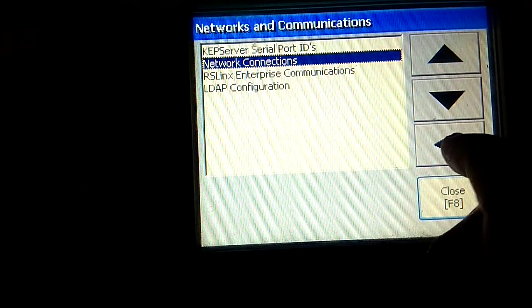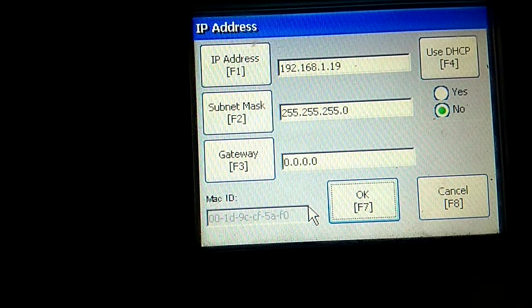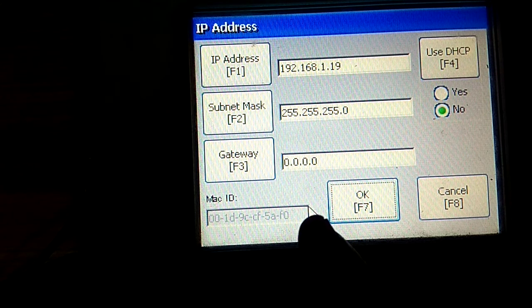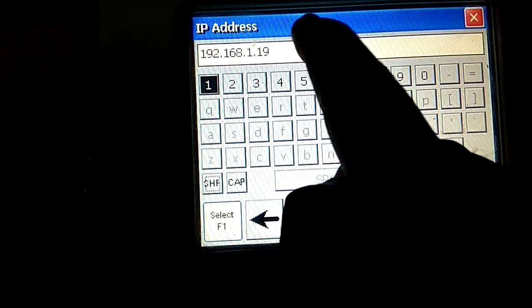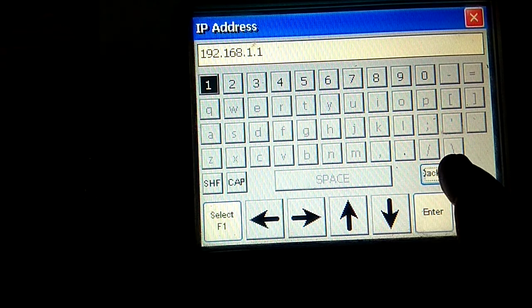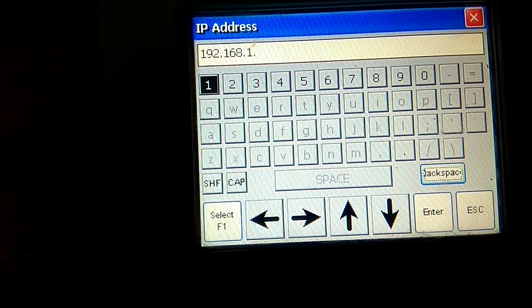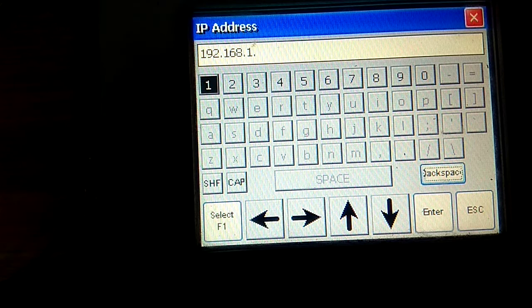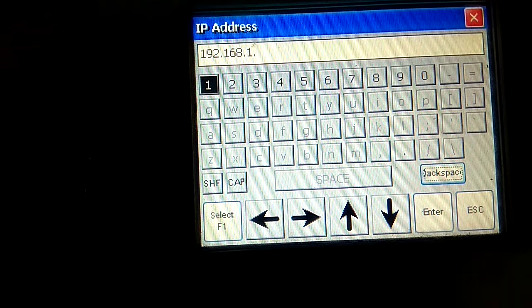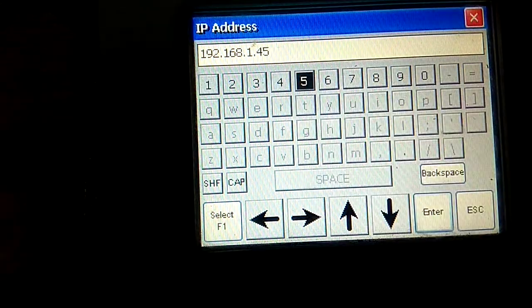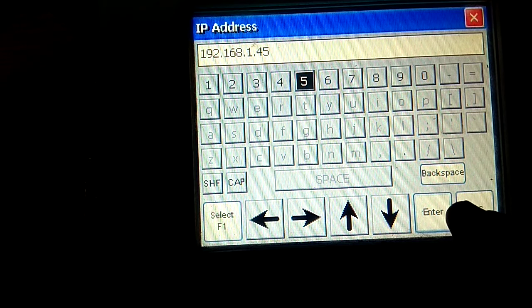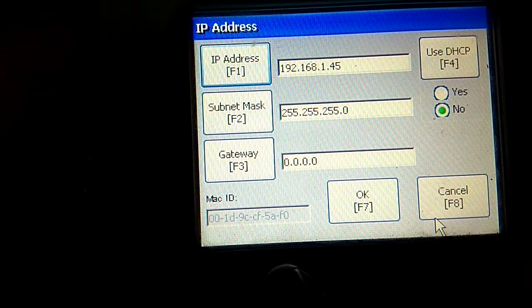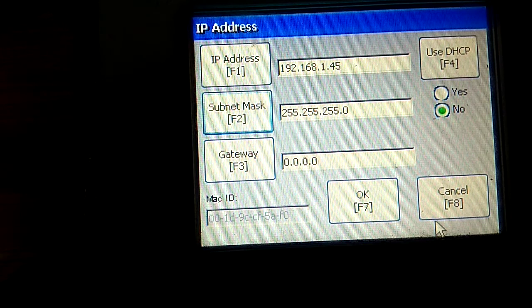Network Connection, Network Identification. Now as you can see, this is showing IP address 192.168.1.19. You can change this IP address to whatever you want - 192.168.1 should be the same with your laptop and your HMI communications, but the last digit should be different. I'm gonna put right now 45, that is 192.168.1.45. Now subnet mask should be 255.255.255.0.